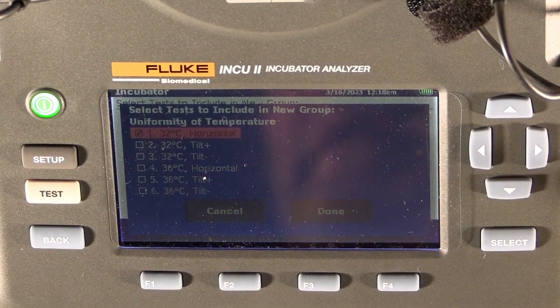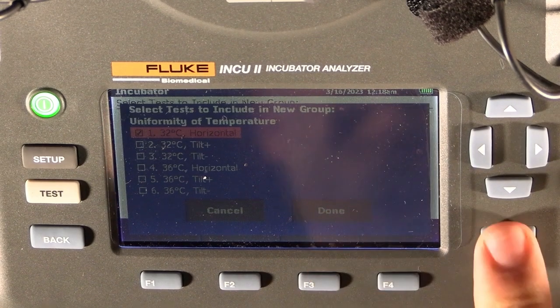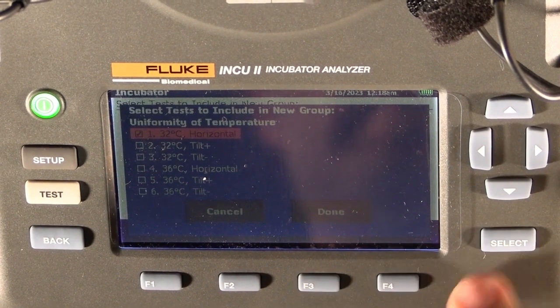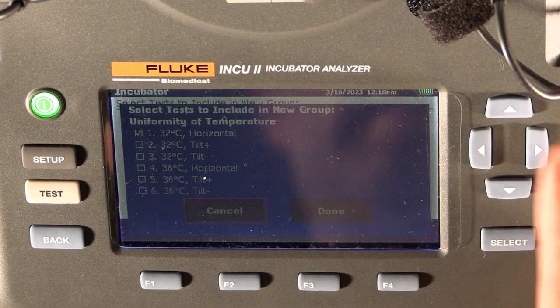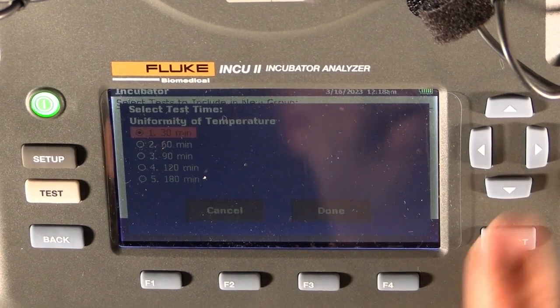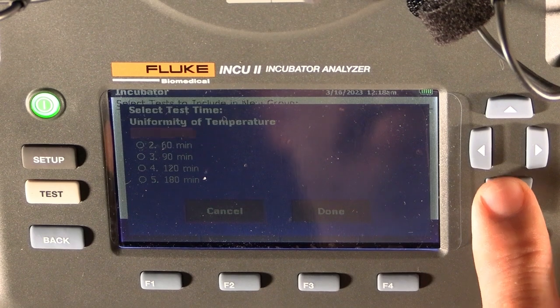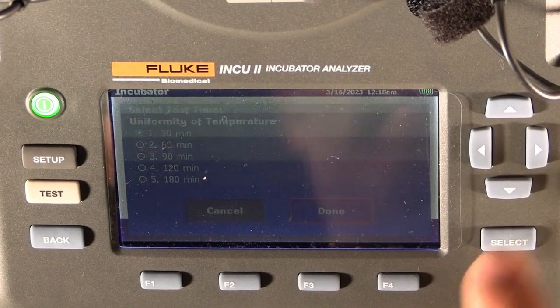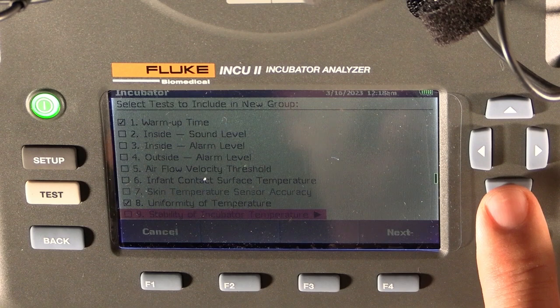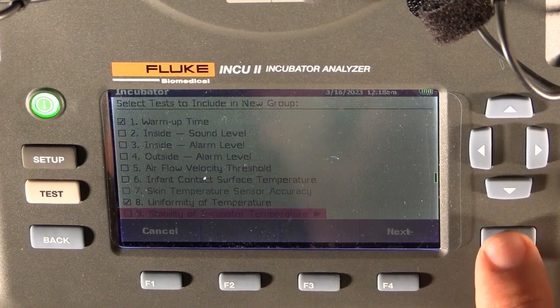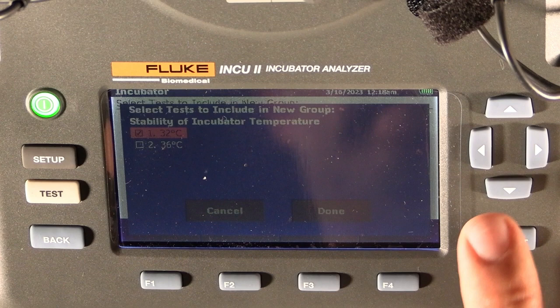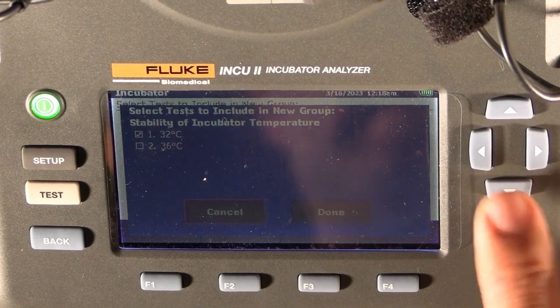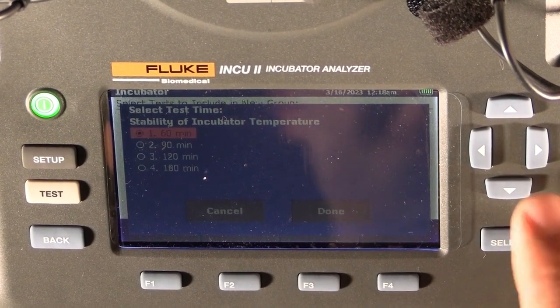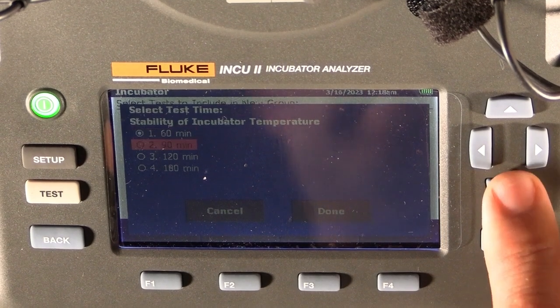So if my incubator's warm-up time test is set at 32 degrees, then I can also do the uniformity test at 32. I can select that, and then once again go down with the arrow and then sideways to get to the done. Same here, go sideways, done. And I can also do the stability test at the same time. So I select that one. Again, I need to choose the temperature. I'm going to use 32, and I'm also going to do it over a period of 60 minutes.